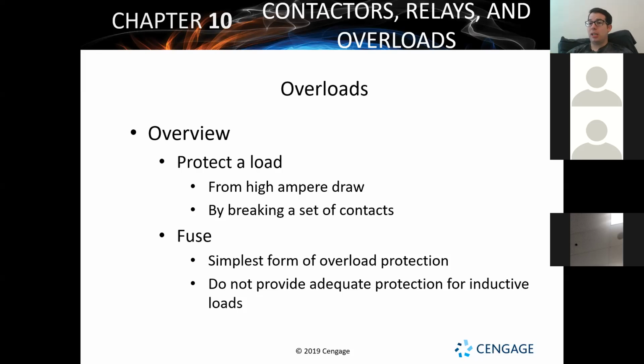If that happens, a technician can go out and check the motors to see why they were overdrawn on amperage. Maybe the start winding is starting to go on a compressor — that's an easy enough fix. We put in a new starting capacitor, installing one that might never have been there.